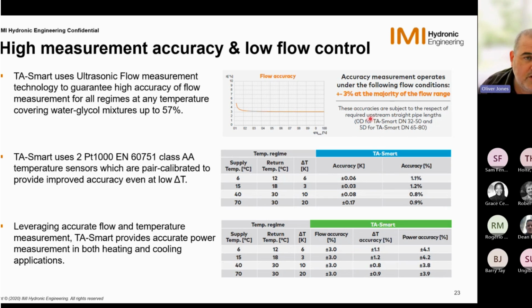And from an installation point of view, for the DN20, although they still say 32 and 80 on the larger ones, so for the DN20 to 50, we are 0 diameters required before the valve, and for the 65 up to 125, we require 5 diameters on those larger size valves. The valve uses 2 PT1000 sensors, as I mentioned previously, and these are class AA. They're calibrated together as a pair and provide improved accuracy at low delta T's. And as you can see from the smart valve itself, from a plus or minus view of a Kelvin, we're within 1% realistically of an accuracy.